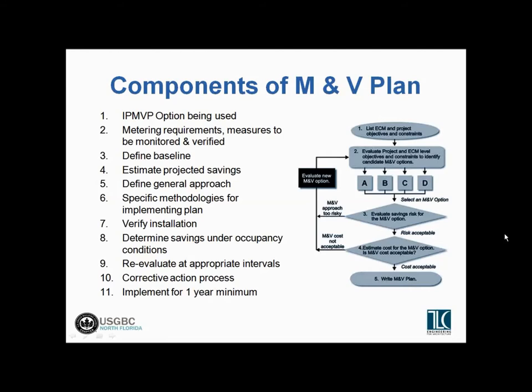The IPMVP — the International Performance Measurement Verification Protocol — is the baseline standard guideline we use for developing measurement and verification plans. What we discuss here is mostly based on Option B, the energy conservation measurement verification approach. This involves identifying how much energy we expected the building and its various systems to use — what was the baseline — and then having the tools, the meters and monitors, within the building to isolate how much lighting energy, heating energy, fan power energy, and cooling energy we're using, to quantify how much each major energy user consumes, let's say, every month.